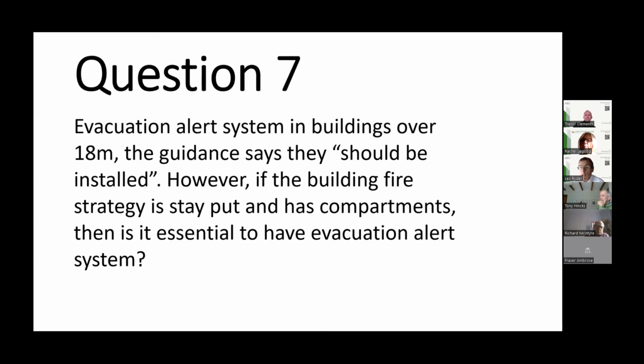They would have evacuated if they could, but being in the heat of battle is a different situation to being in a courtroom 6 or 7 months afterwards, suggesting that this and that should have happened. Basically what this guidance provides is that the fire authority can, at the point where they think compartmentation is going to be breached, or even if they anticipate it being breached, use a communication system to each floor of the building, whereby they can ask the occupants to evacuate rather than hold them in position. And it's a direct result of Grenfell.